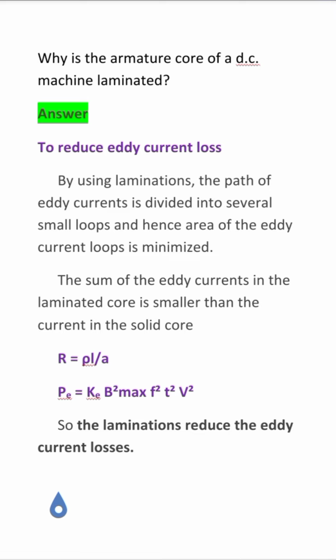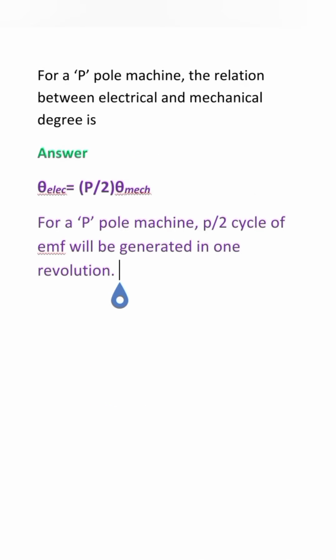Another point we note is that eddy current loss is directly proportional to the square of the thickness of the lamination. In order to reduce eddy current loss, the thickness of the lamination should be kept as small as possible. For a P-pole machine, the relation between electrical and mechanical degree is: theta electrical degree is equal to P by 2 into theta mechanical degree. Why? Because for a P-pole machine, P by 2 cycles of EMF will be generated in one revolution of the rotor.